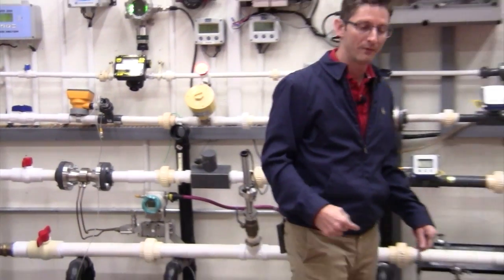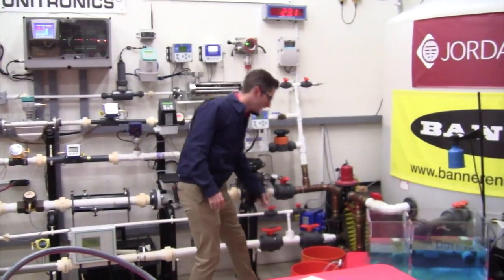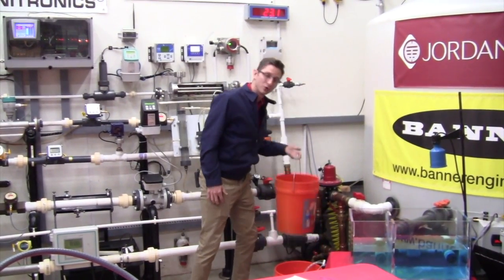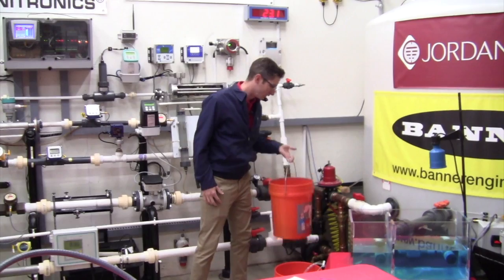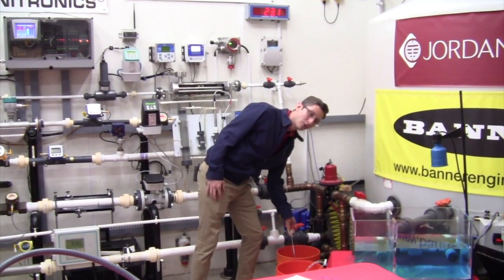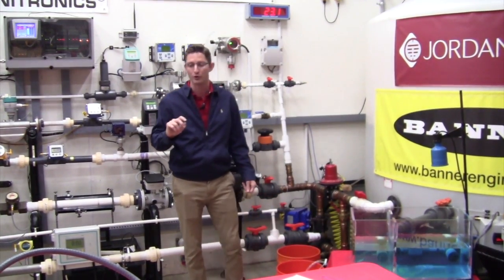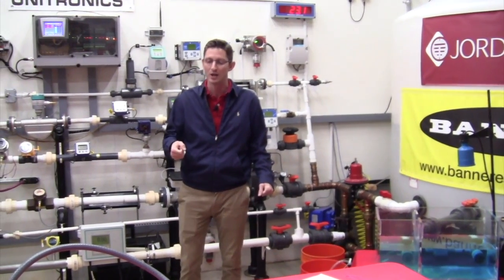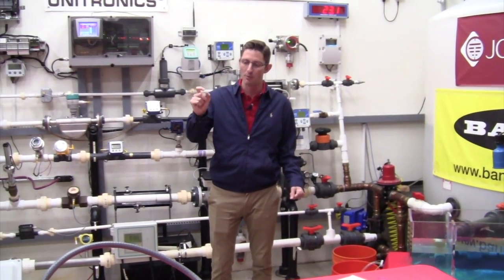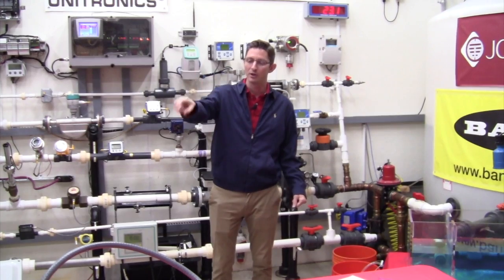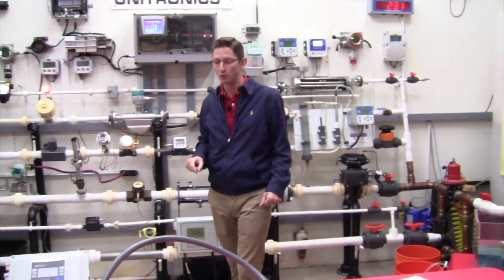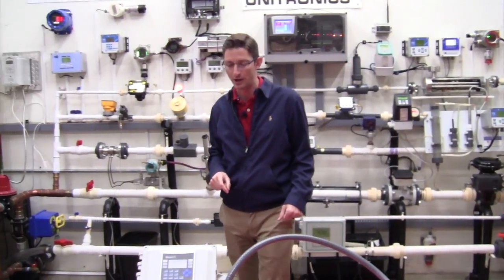We also have a 5-gallon bucket, which is what we're going to fill up. So once we fill 5 gallons up, that'll be equivalent to 2 of your 2.5-gallon jugs. And then I will show you how we go about calculating the math and the K factor that we need to program into the display.